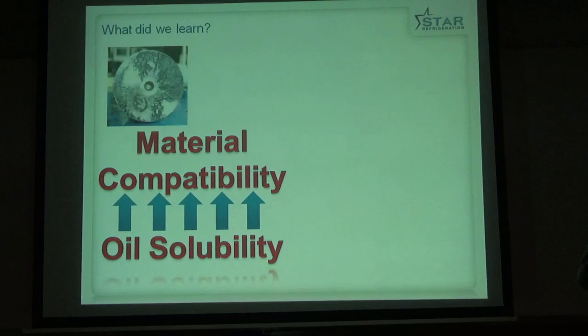There was a challenge with oil solubility. Everybody knows that ammonia is insoluble in oil, except that when you go to these high temperatures and pressures, we find solubility about 4%. This is an aluminium balance piston from inside one of the screw compressors. And what's actually been happening here is that the ammonia has been absorbed in the oil and there's been a vibration between two very close surfaces which has caused cavitation on the surface of the aluminium. It's knocked the protective oxide layer off and we've got this heavy corrosion underneath because of this oil solubility problem. So we've had to look at alternative materials for some of the components in the compressor.